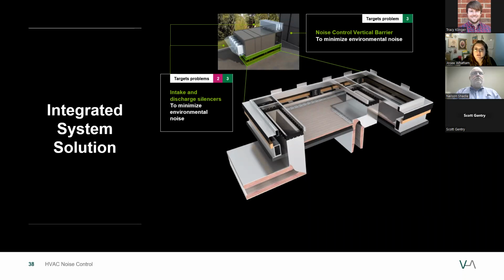Intake and discharge silencers are designed to minimize pressure drop and resist corrosion due to the outdoor environment. Noise barriers also prevent property line noise problems, and they act as architectural screening as well as an effective noise control that does not reduce equipment performance.